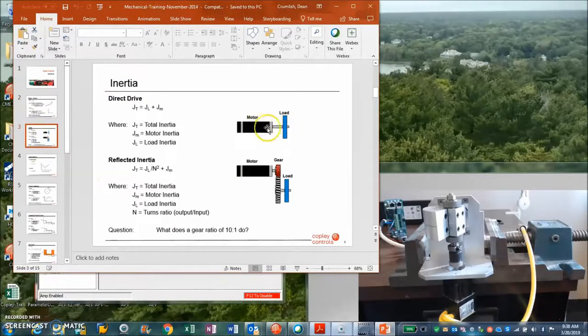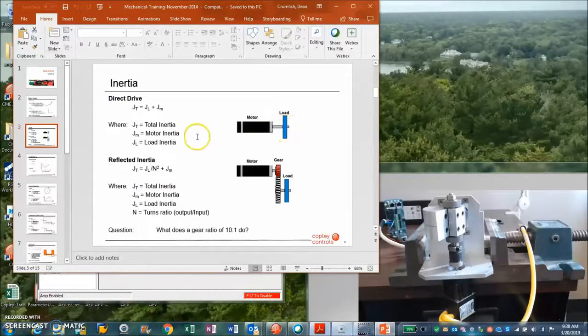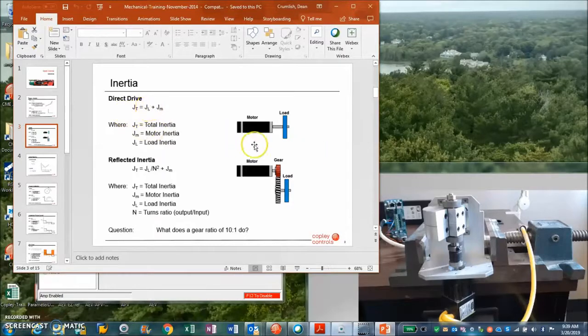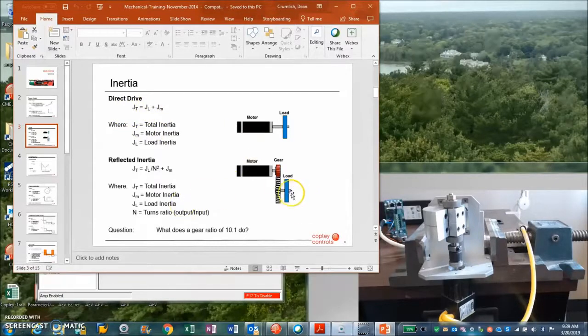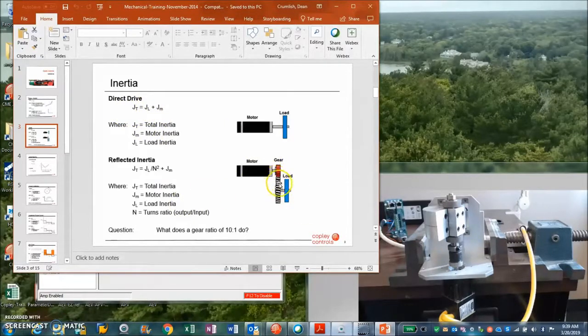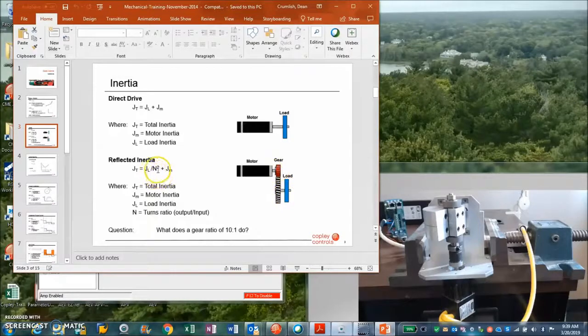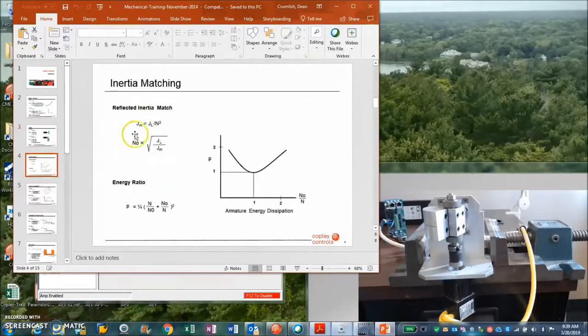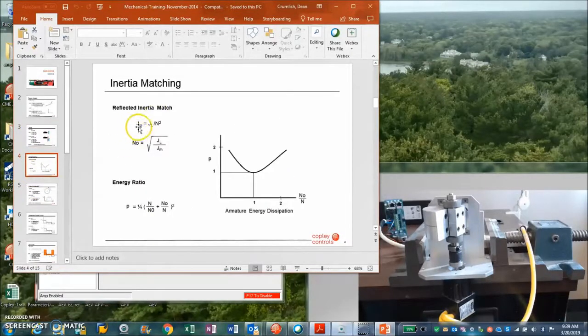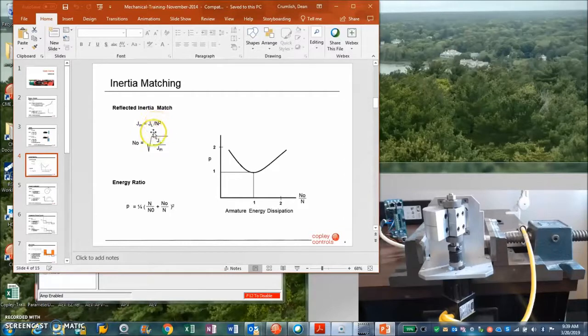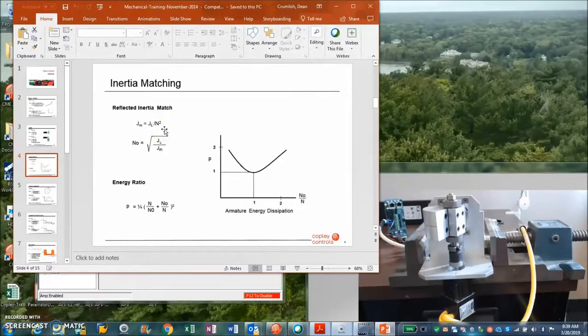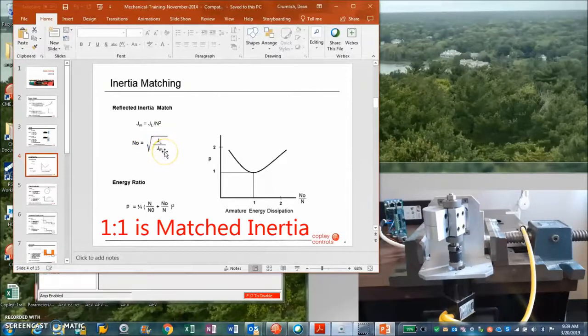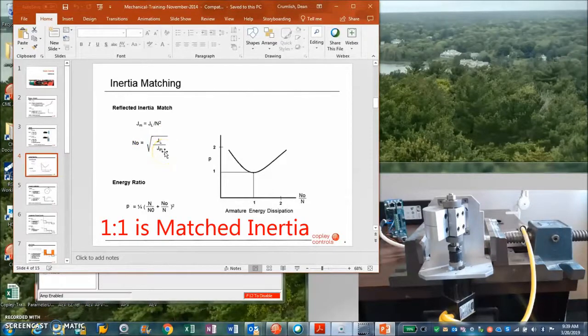Direct coupling is the motor inertia plus the load inertia equals the total inertia, but a gear ratio can reduce the reflected inertia by a square law. We can see the motor inertia equals the load inertia divided by some gear ratio squared, so we can calculate the square root of the load over the motor to get the number ratio of turns for the gear to make it inertia matching.